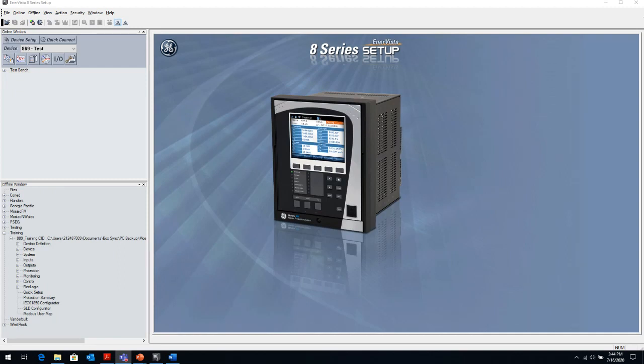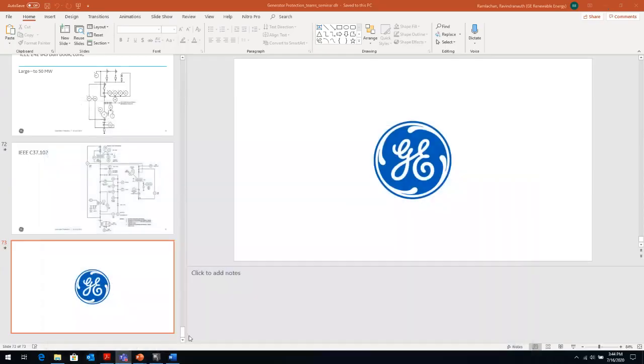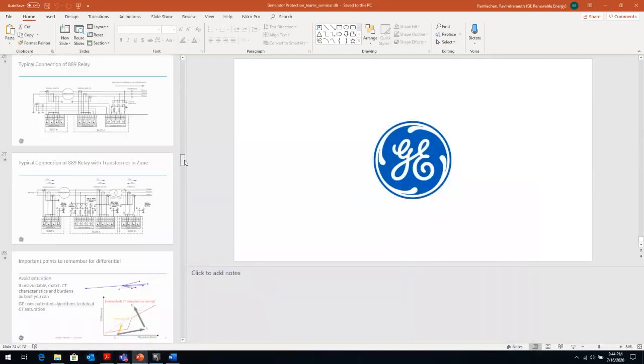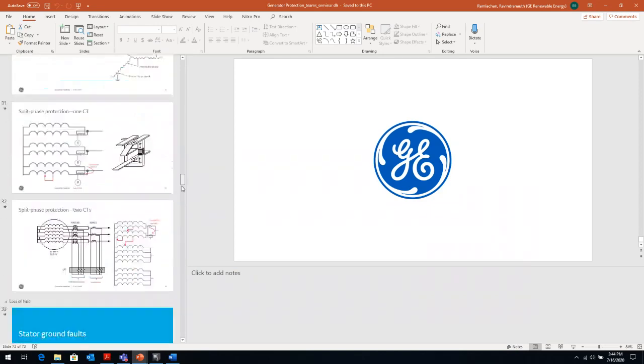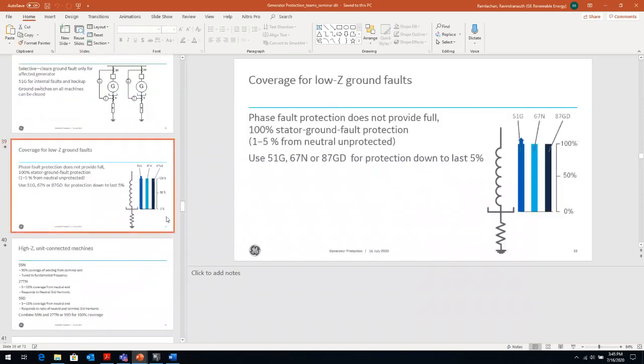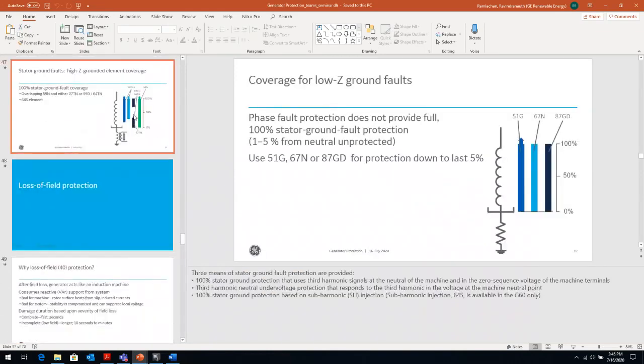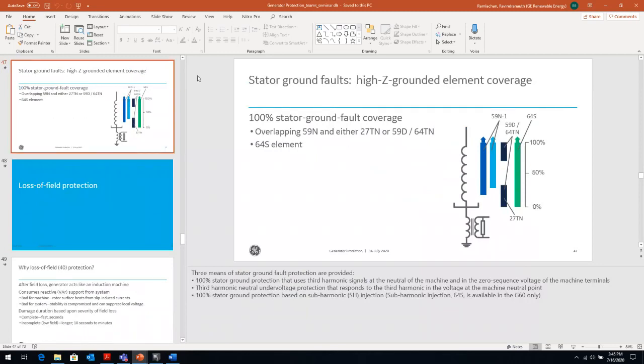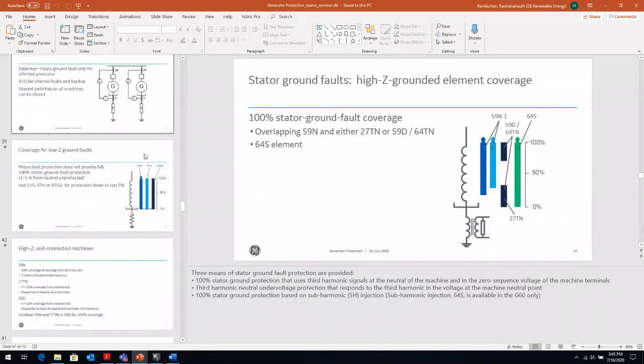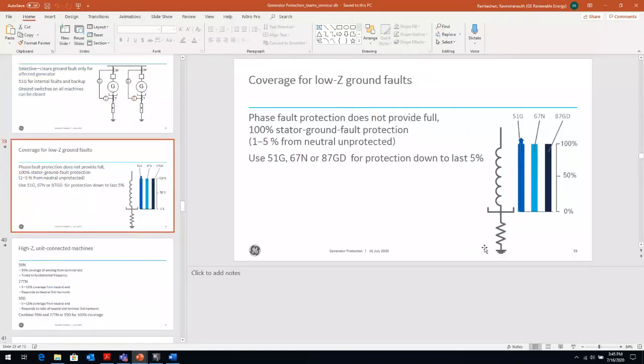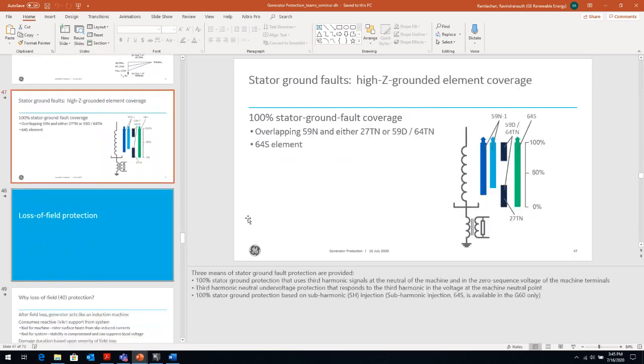So one of the questions I get a lot when we talk about generator protection, for a high impedance grounded generator, is about the coverage for ground faults up to 100% of the winding. I talked about it for low impedance and high impedance. Why does it not matter much in low impedance? If it's solidly or low impedance grounded and the fault is close to the neutral, you don't see neutral current, so that's not a problem there. Is it a problem on the high impedance grounded? Say I have a ground fault at the neutral point. Do I really need to detect that fault?